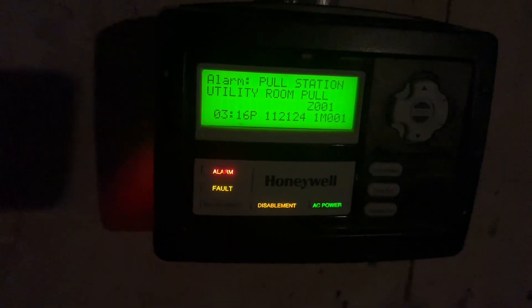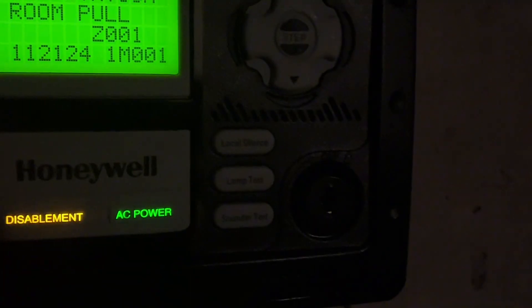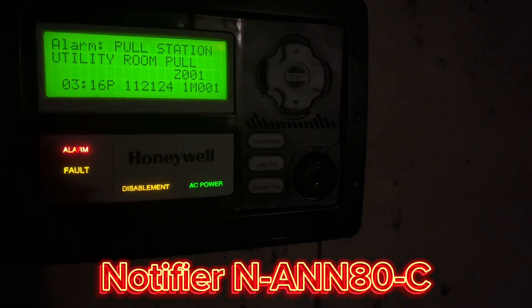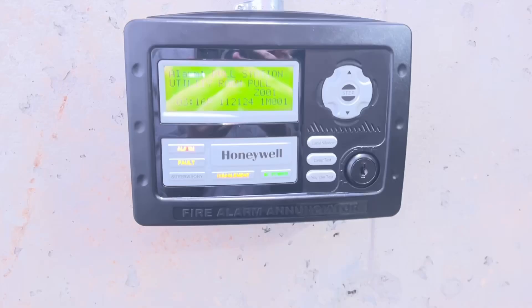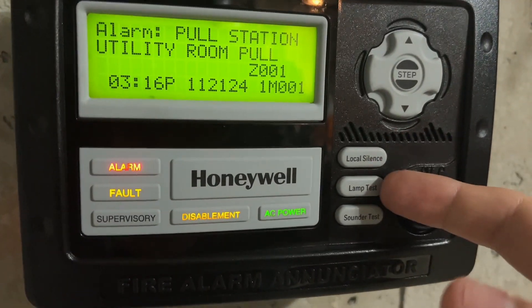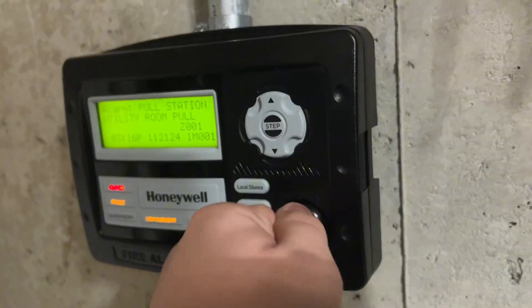Buttons make noise, which is nice. You can see that the functions, like I said earlier, are different. Now, this is technically a rebrand of the Notifier ANN-80C. Basically, that annunciator does not allow you to control the system. So you can see it just has step, local silence, lamp test, sounder test. But it works like a regular ANN-80, which is nice because I got it for $20.